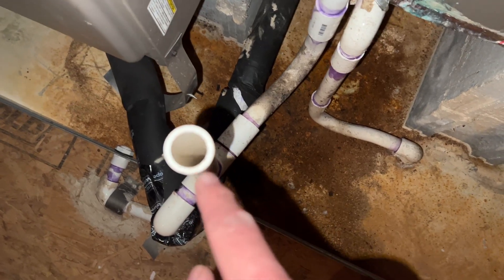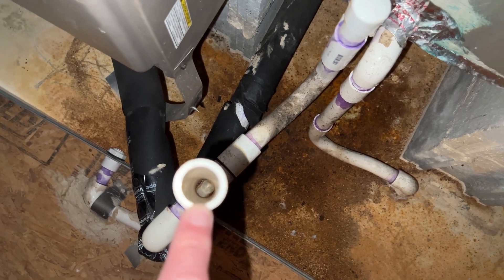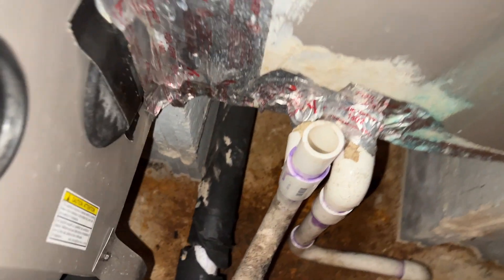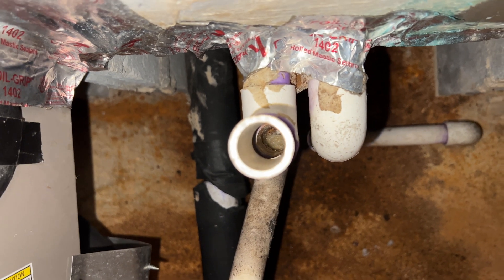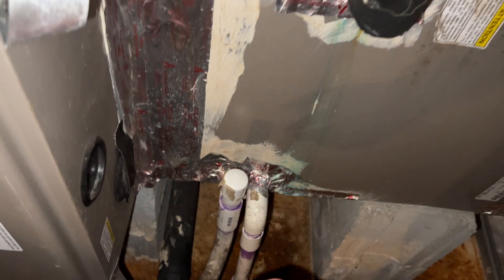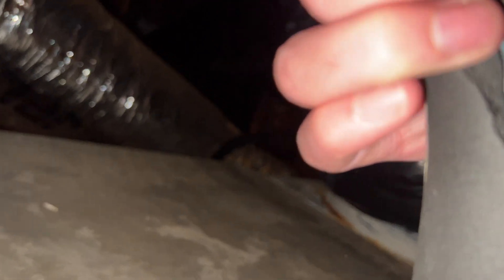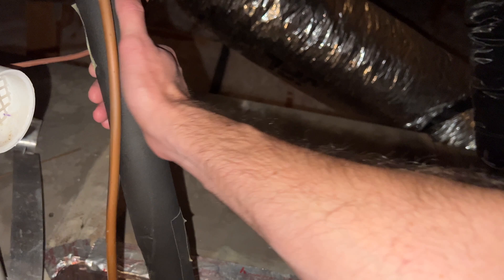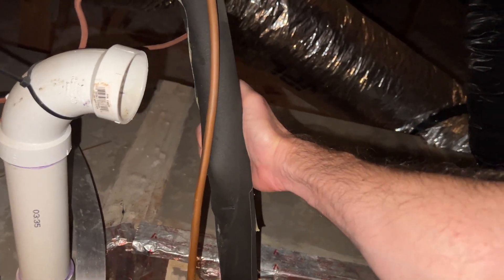If you look in this little vent hole you should see water running, and I don't see water running. I'm gonna pull this — I feel air, which is good, but no water. That means it's probably not locked up. I'm gonna see if I can find the line inside here — check if it's cold — and it's not, it's warm. The fact that this line is warm tells me that the problem is outside.